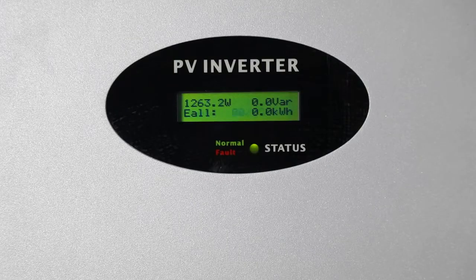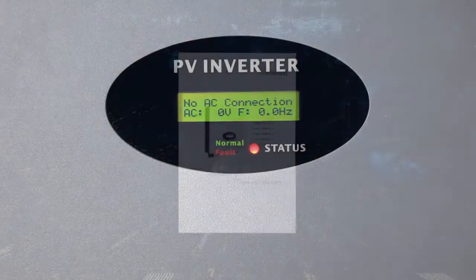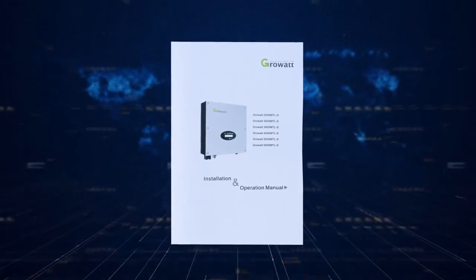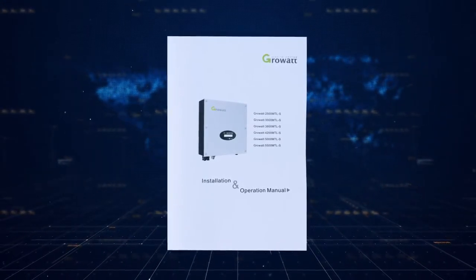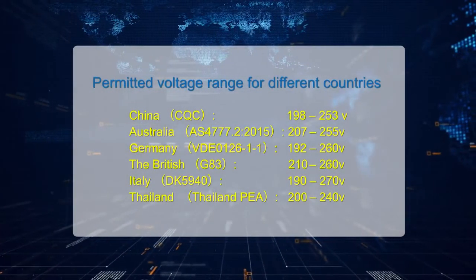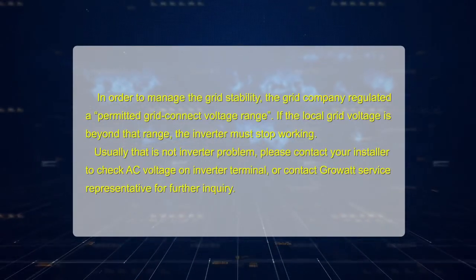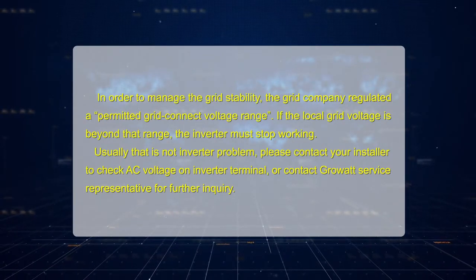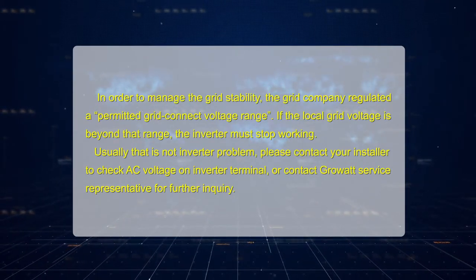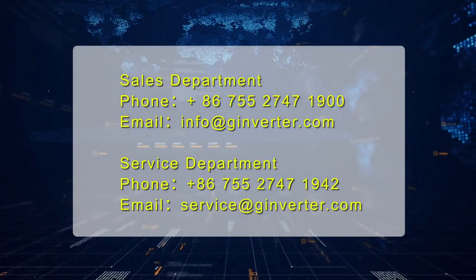The inverter will show an error message or error code on its LCD screen if a fault occurs. Please refer to the user manual for the complete fault list and descriptions. There is also a detailed troubleshooting guide available on the Growatt website. To manage grid stability, the grid company regulates a permitted grid connection voltage range. If the local grid voltage is beyond that range, the inverter must stop working. Usually that is not an inverter problem. Please contact your installer to check the AC voltage on the inverter terminal, or contact a Growatt Service Representative for further inquiry.